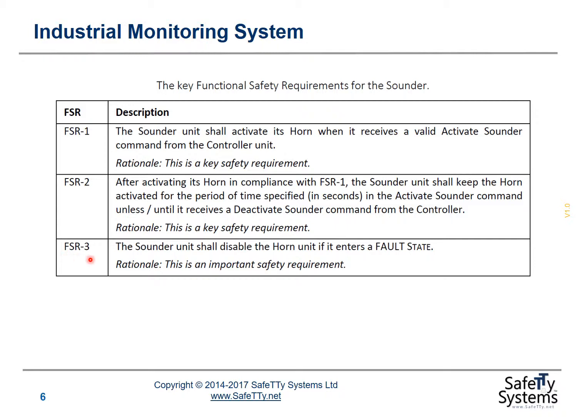Functional safety requirement three: the sounder shall disable the horn if it enters a fault state. This is clearly an important safety requirement — if we keep getting false alarms from our sounder unit, we'll have much less faith when we get a real alarm and may not believe it's valid, which may have dangerous consequences. So it's important that the alarm sounds when commanded, sounds for the correct period of time, and does not go off when it's not intended to. These are all important safety considerations.